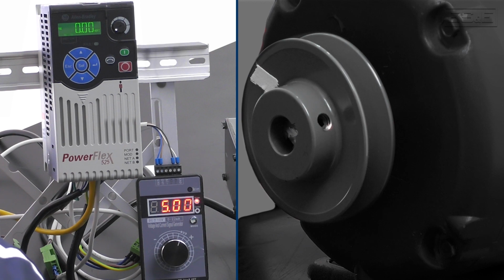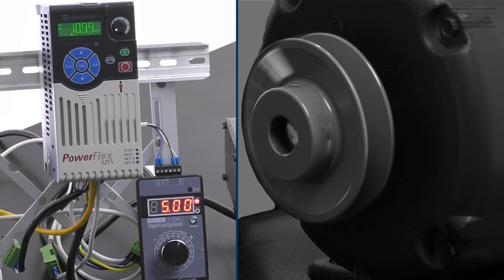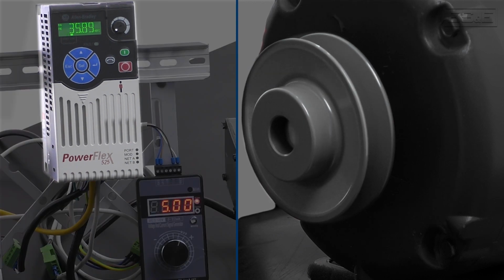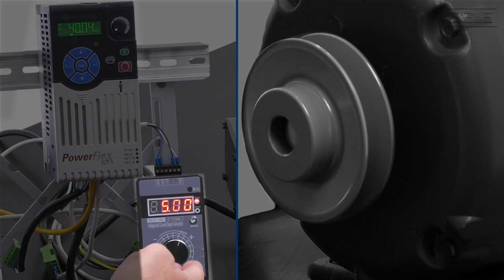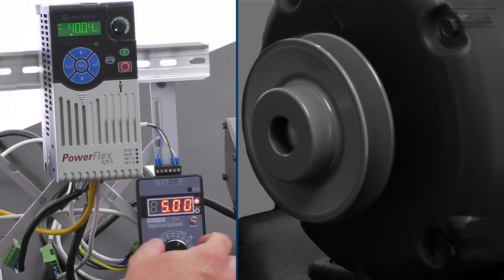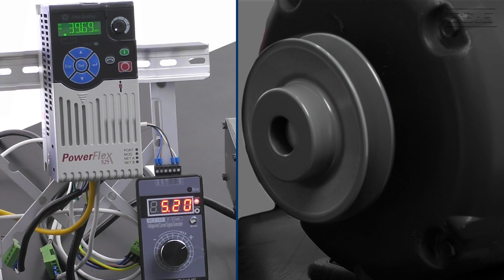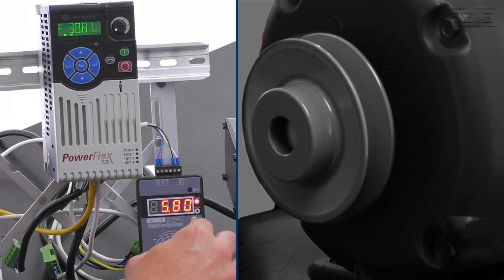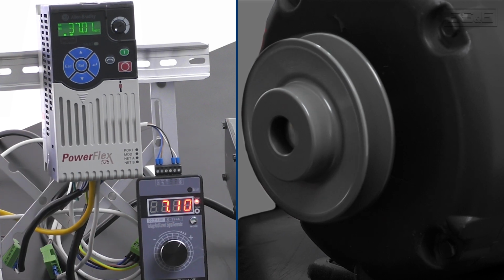Okay, we're going to start the drive. The keypad frequency is set for 40 hertz, as you can see. The analog input here is set for 5 volts. As I increase the voltage of the analog input, you'll notice that the frequency is going down. So we're actually slowing the motor. We'll keep increasing. As you can see, it will not go below 37 hertz, which is 3 hertz below the 40.